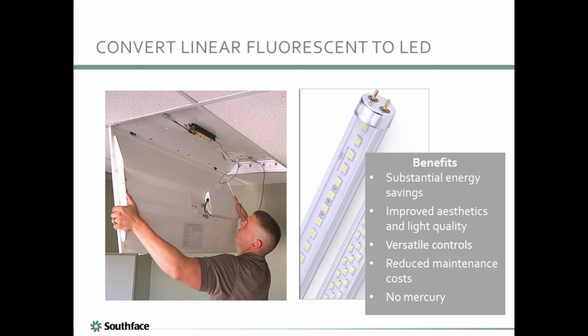There are 3 different options for upgrading existing linear fluorescent fixtures to LED. The first option is an entirely new LED troffer. A new LED fixture provides excellent efficiency, full dimming, long lifespan, and it looks great. However, this is the most expensive upgrade option, typically more than $250 per fixture. Consider using a new LED troffer if dimming and daylighting controls are required. It also may make sense when moving from a T12 to LED.